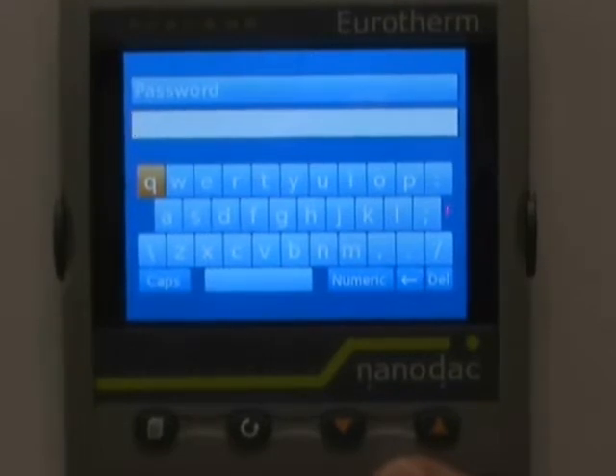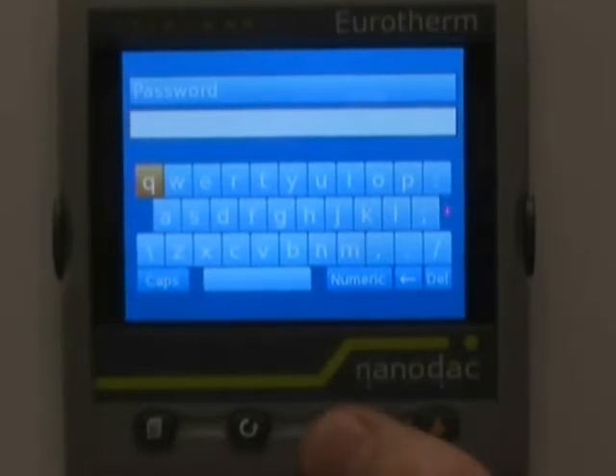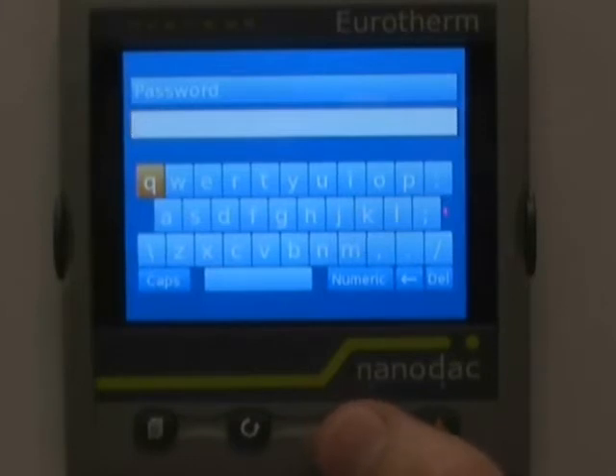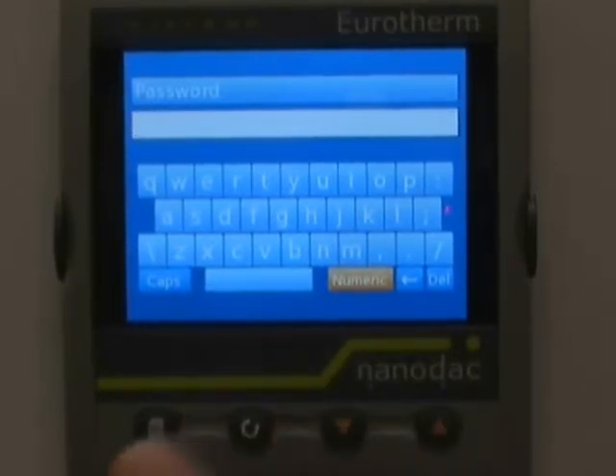The default password for the NanoDAC is 100. As you can see, there are no numeric digits on the screen, so we need to change the keyboard to numeric. Hit the left arrow — it requires a few less keystrokes. Hit it three times and you'll notice Numeric is highlighted; hit the scroll key once.